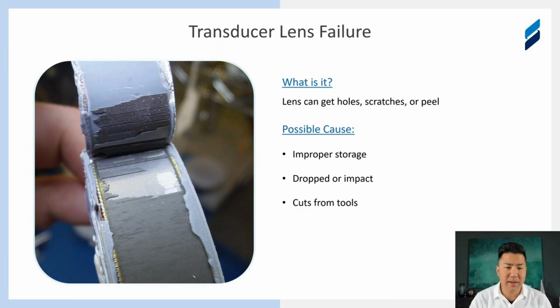And also cuts. These are used in the healthcare environment, and they're around sharp things, so they could get cut on the lens. And again, when you apply gel to this transducer, it'll start getting in there and really eroding away all the adhesive properties of the lens itself. In this particular case, being pretty severe, we have this, you see here as I'm circling it. The gray matter is actually the top of the crystal. And so you can see sometimes when the lens damage is so severe that the crystal is actually breaking away and adhering to the lens that's separating, and this is going to cause some massive problems in your image quality.